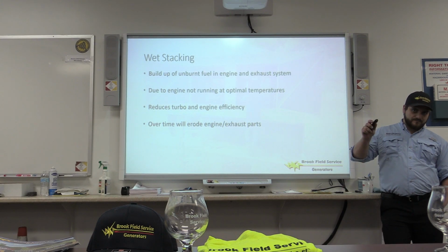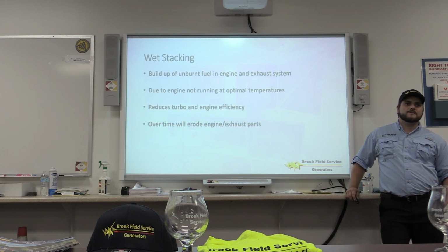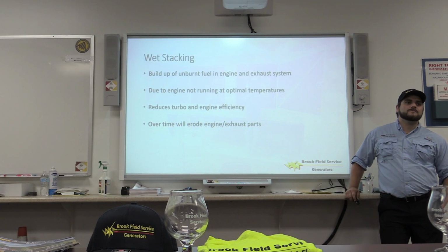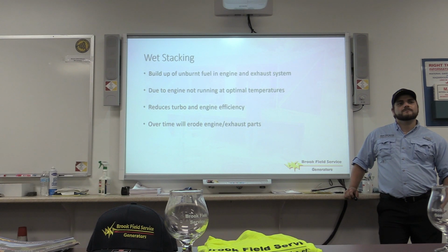Right. And if I'm jumping ahead on this, feel free to cut me off. That's the big thing on the diesel units: if you can do a monthly load test, run your whole plant for an hour, help them burn out, that's the best thing for them. If you're just running no load all the time, they're going to wet stack. But the new ones do have regeneration built into them. So that also plays a factor in where you put a generator: farther away from the buildings, farther away from trees and stuff, because of that extreme heat.